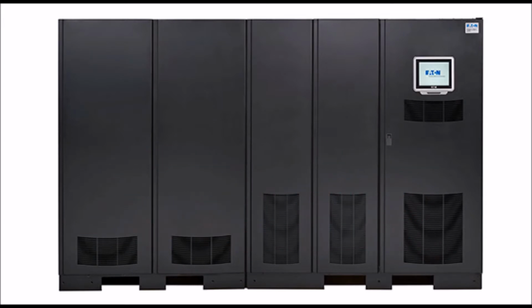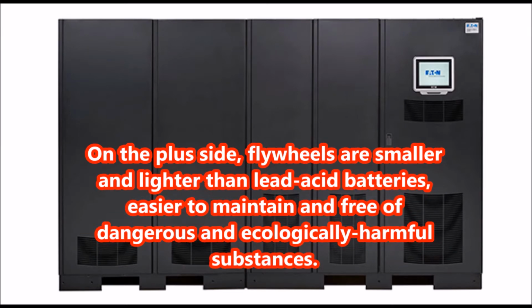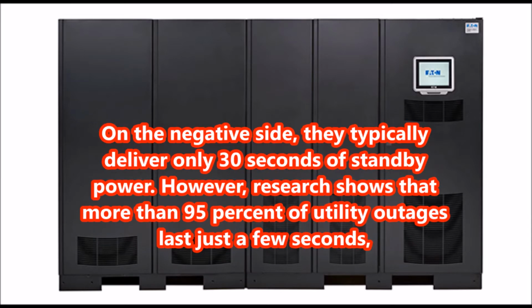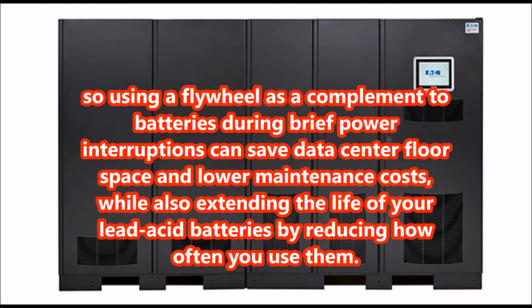moving altogether. On the plus side, flywheels are smaller and lighter than lead-acid batteries, easier to maintain and free of dangerous and ecologically harmful substances. On the negative side, they typically deliver only 30 seconds of standby power. However, research shows that more than 95% of utility outages last just a few seconds, so using a flywheel as a complement to batteries during brief power interruptions can save data center floor space and lower maintenance costs, while also extending the life of your lead-acid batteries by reducing how often you use them.